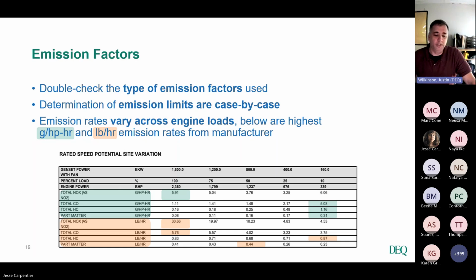One thing I want to note is that facilities will come to us and want to use the tier values for EPA certifications, but that's just not appropriate. Tier certifications and tier values are weighted average values. If you're in a real pinch, you can use those. The NSPS Quad I allows you to apply a 25% factor onto it, and you can use those for case-by-case emissions limit determinations. But for us, we have not really struggled with being able to get the manufacturer certifications.